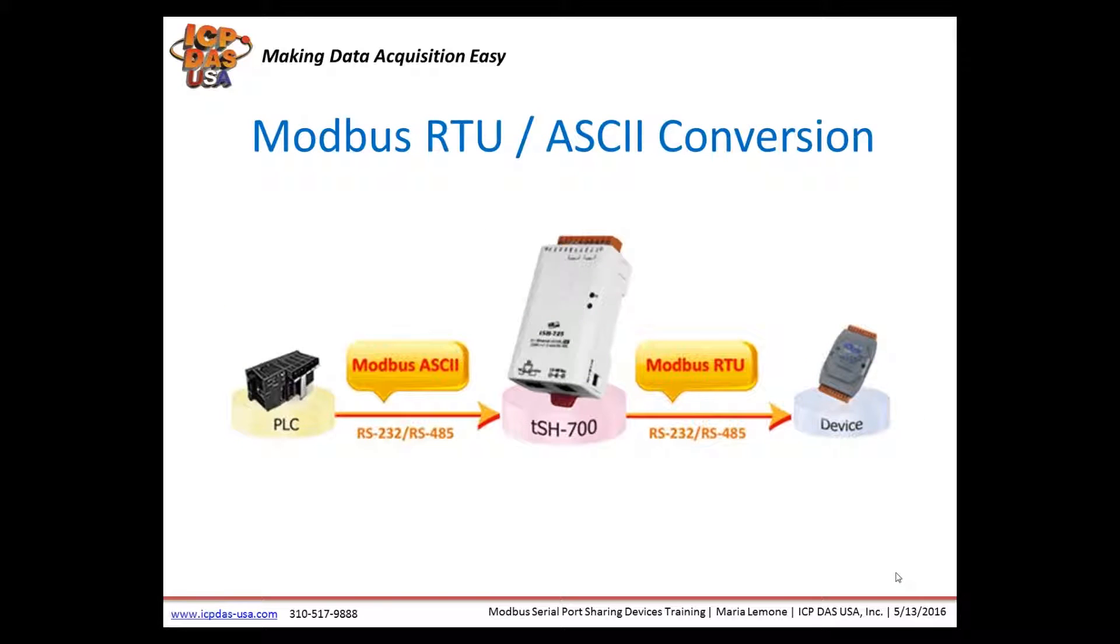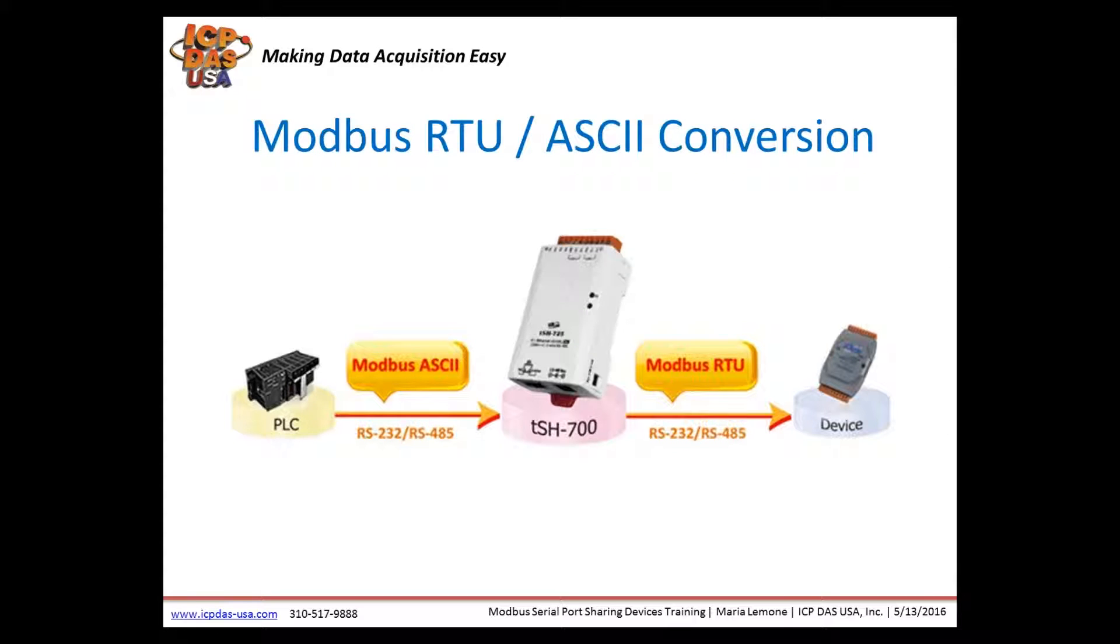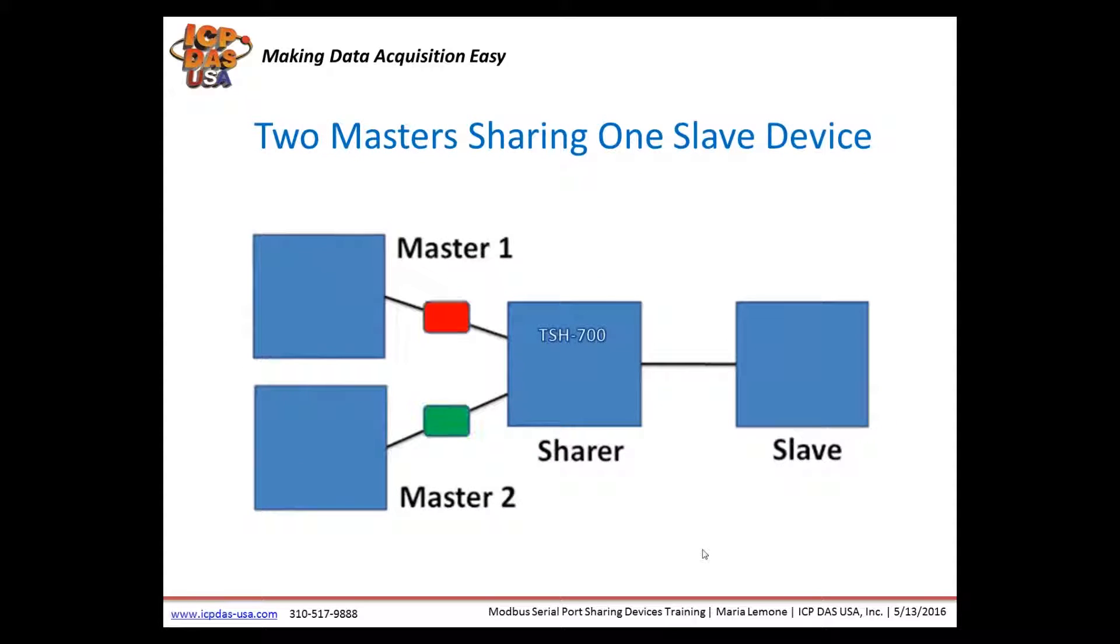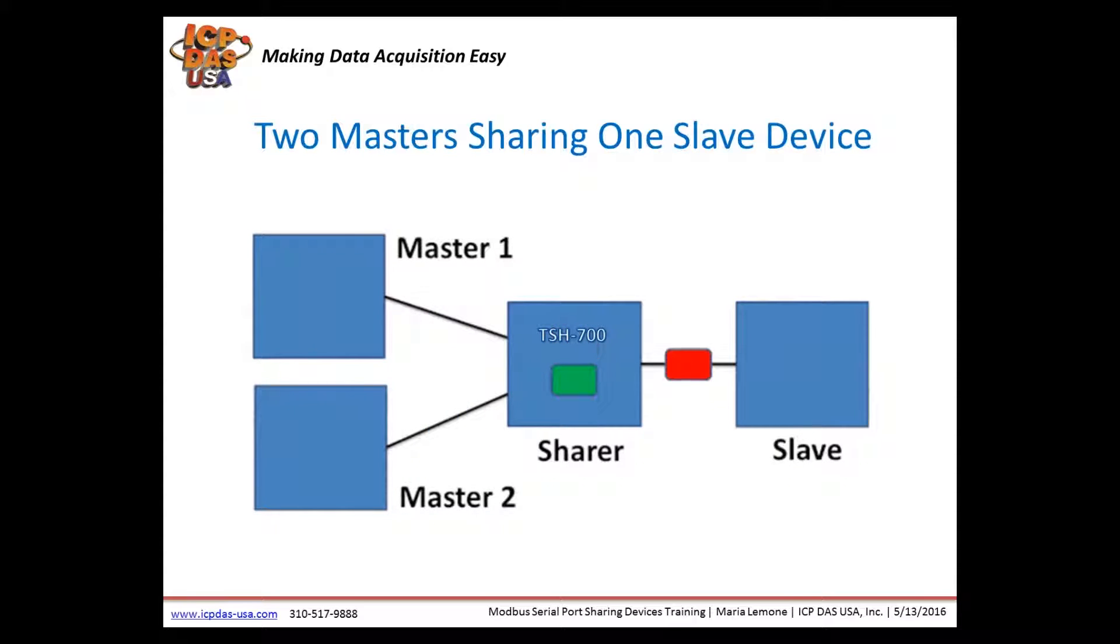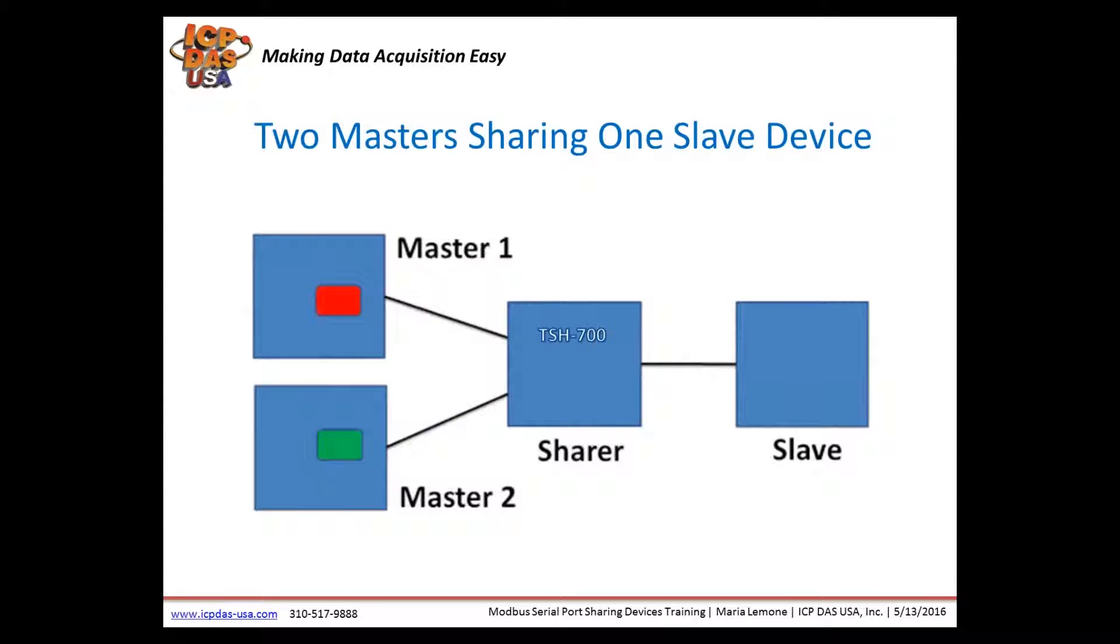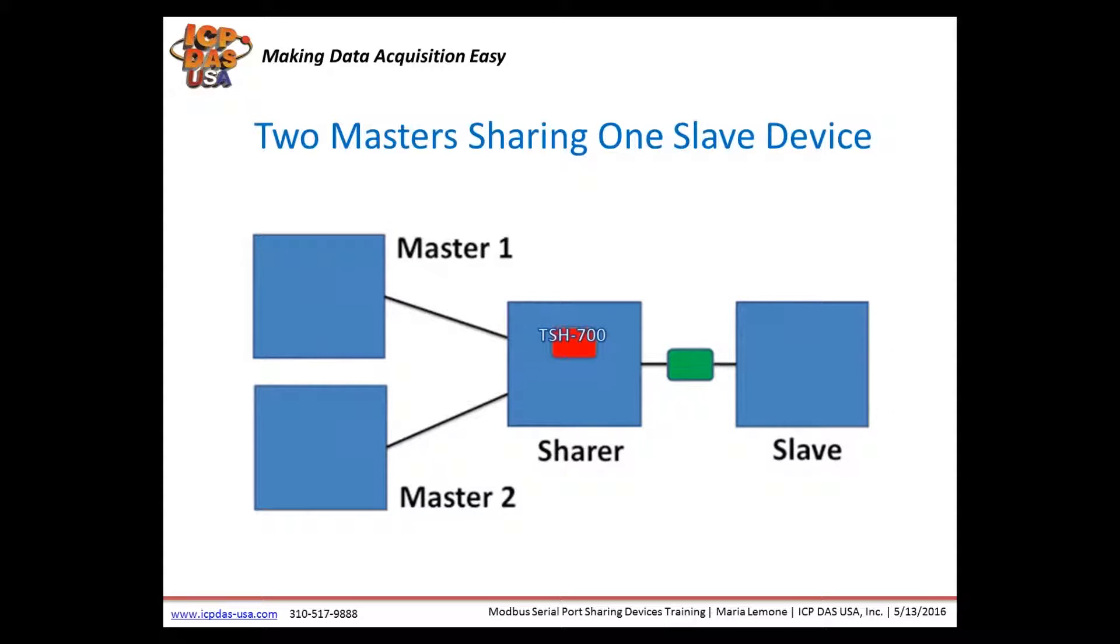Our new TSH-700 serial port sharing devices work with half-duplex and full-duplex devices. They feature a baud rate conversion function which allows a single master to communicate with slave devices using different baud rates and data formats. Modbus mode can be used to convert Modbus RTU and ASCII protocol. Raw data mode can be used for DCON or other query response protocols. Different baud rates and different formats can be used on different serial ports.